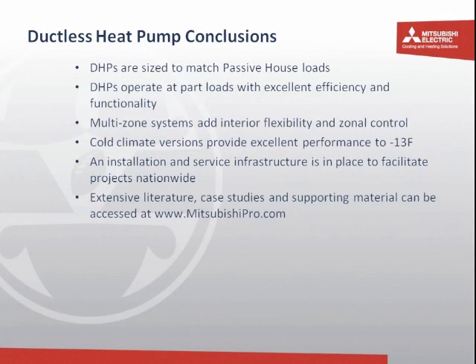What we really recommend is if the space is not occupied, the system should be off, because there's, again, the energy efficiency benefit of the system is that it operates completely independent of the central system, and the inverter with the excessive capacity beyond nominal allows you to take a space that's considerably out of set point and bring it back into condition quickly. So the first answer to this would be turn the system off, and then when you're occupying that space, let it decide what mode it needs to be in and get you to the conditions that you need quickly.